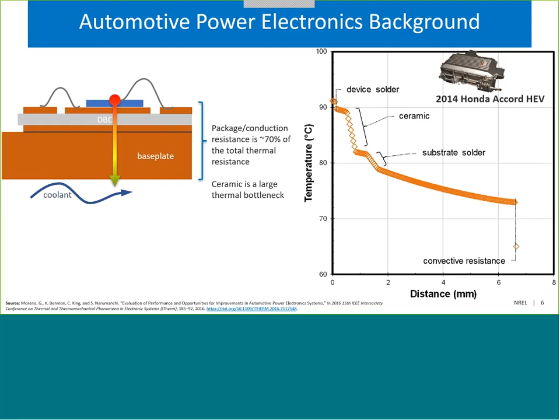Okay, the reason we're conducting this research is because thermal management is essential to increase the power density and the reliability in all electronic systems. The specific objective for this project is to develop thermal management techniques to enable achieving the year 2025 Department of Energy's power density target of 100 kilowatts per liter. Using wide bandgap devices enables us to achieve this target because they are more efficient and can operate at higher temperatures. The challenge is to create thermal solutions that allow for packaging of high temperature, wide bandgap power electronics in close proximity to capacitors that typically cannot exceed about 100 degrees C, although there are advances in capacitors that are pushing that temperature limit. Automotive applications are typically about 100 degrees C.